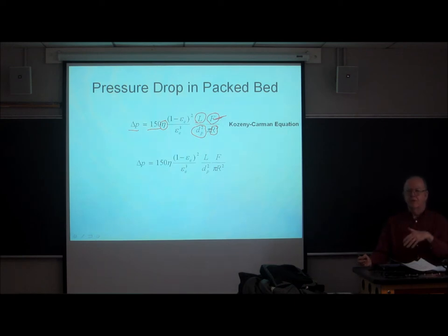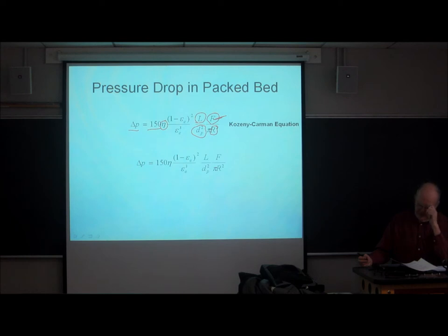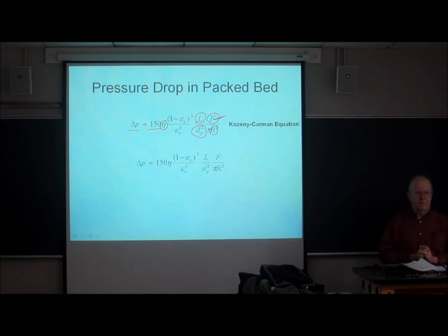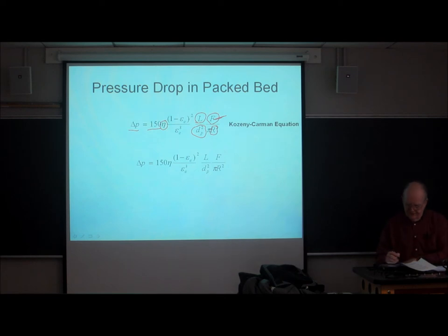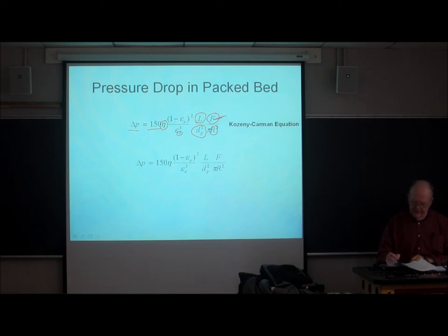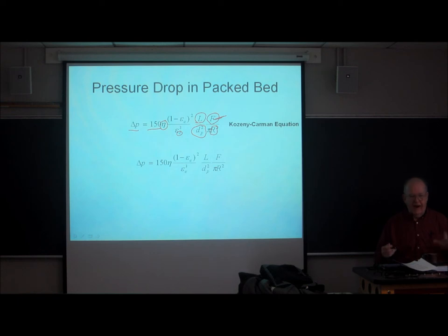The change from 3 micron particles to 1.7–1.8 micron particles crossed that barrier and required higher pressures. Try making something that delivers an absolutely constant flow rate at 1,200 bar without leaking — it's challenging. The interstitial porosity also matters with its (1 minus epsilon)² over epsilon³ dependence, meaning how the particles are packed has an appreciable effect on the measured pressure drop.